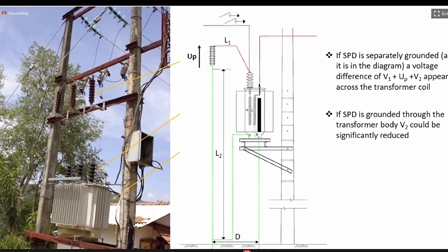Now, in countries like South Asia, we see that there are transformers. For example, in this picture, most probably somebody can touch the cross iron bars of this transformer. It may be just 1.5 meters above ground level. Now imagine that the neutral voltage is transferred to the body, and in turn transferred to these cross iron bars. So if somebody touches that, he may definitely be killed.